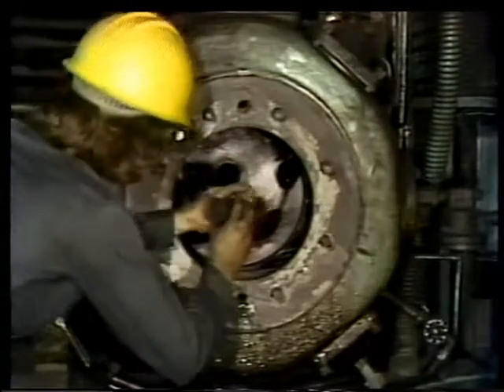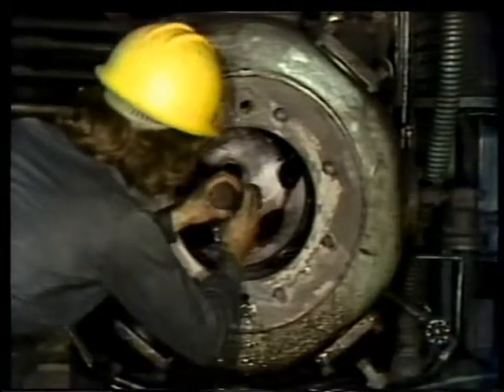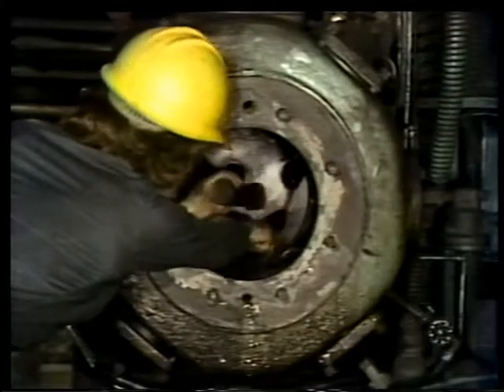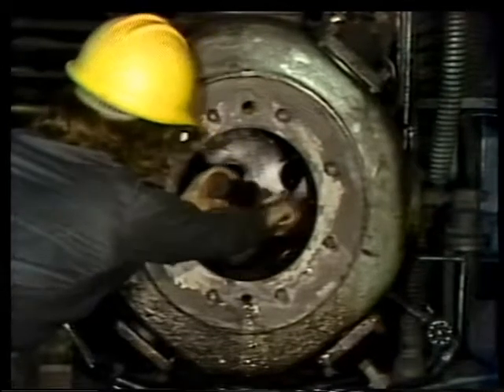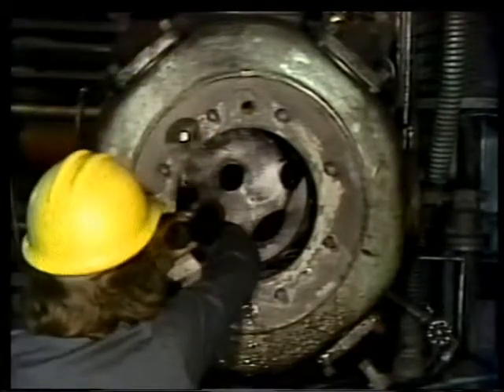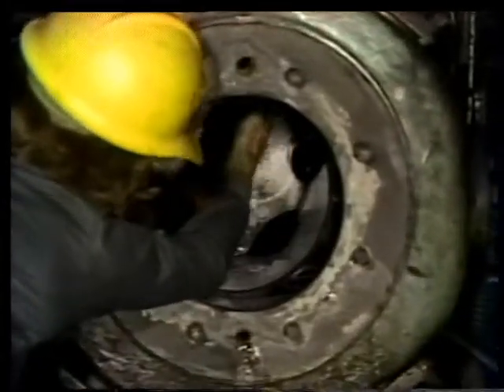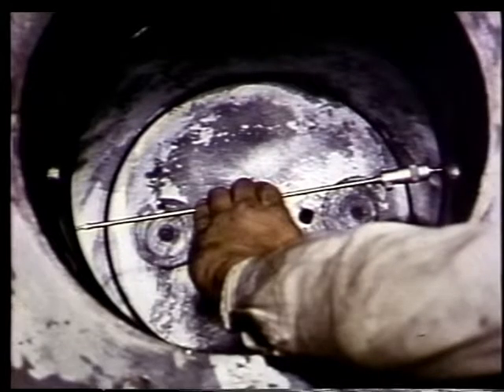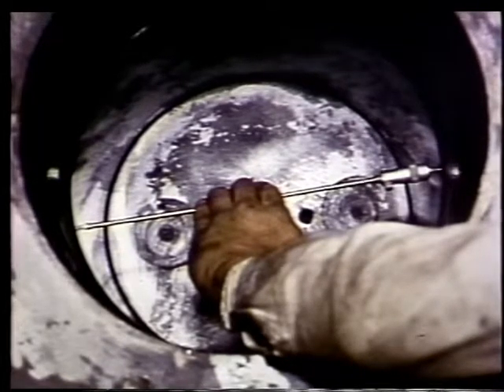Now you need to inspect the cylinder. Look for a lack of lube oil, a scored cylinder, excessive carbon buildup, and any other indications of damage. An inside micrometer is used to check to see whether or not the cylinder is out of round. This check should include the entire length of the cylinder to make sure that the cylinder isn't tapered. These readings are compared with the manufacturer's specifications.